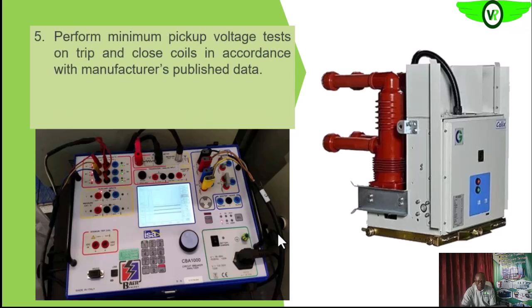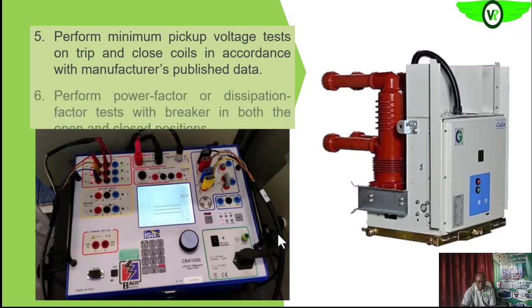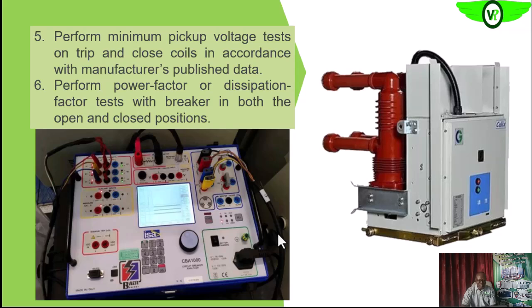The next test that you will do using the circuit breaker analyzer is the minimum pickup voltage test on the trip coil and the closing coil of the circuit breaker. Then you also want to perform power factor tests or dissipation factor tests. If you are not yet familiar with power factor testing procedures, you can look at the description below for a link to the video training on power factor testing. During the power factor test, you will be testing the insulation between phases of the circuit breaker and between phase and ground.